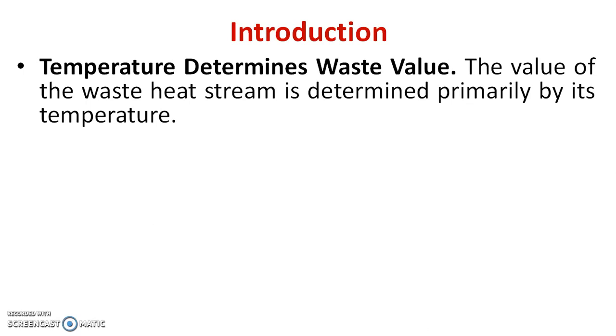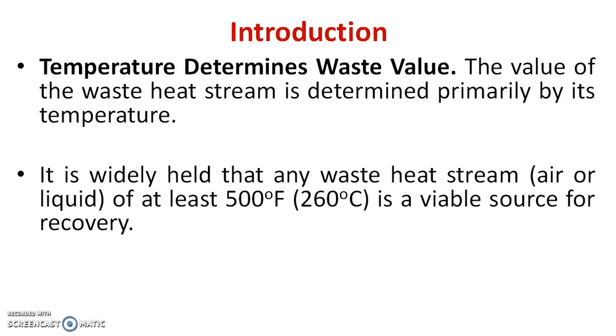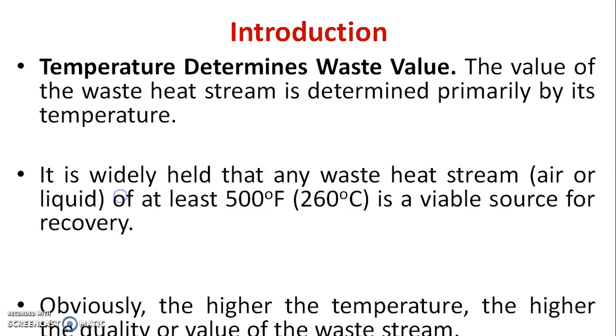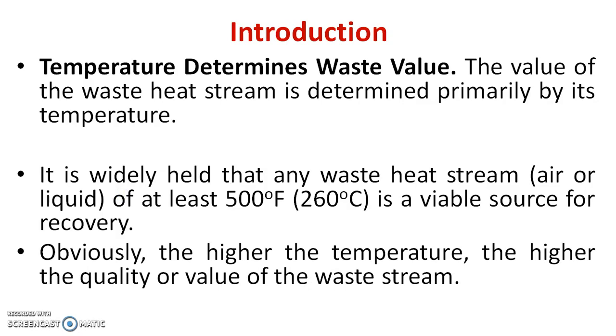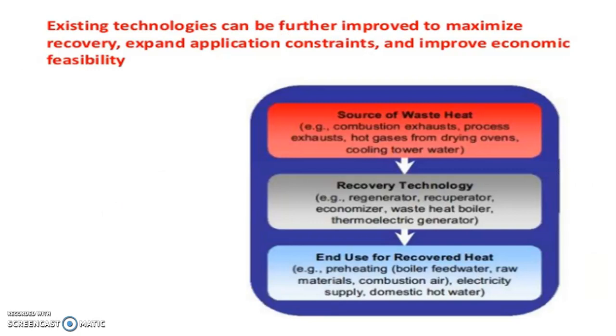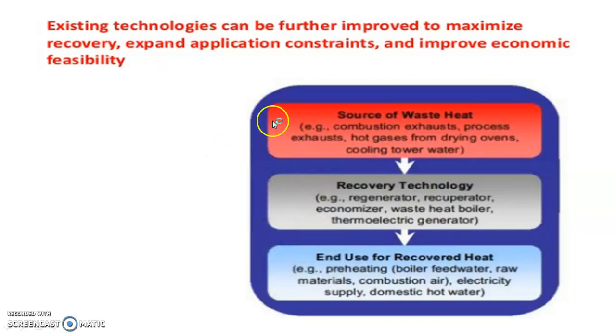Temperature determines waste heat value. The value of the waste heat stream is determined primarily by its temperature. It is widely held that any waste heat stream of at least 260 degrees centigrade or 500 degrees Fahrenheit is a viable source for recovery. Obviously, the higher the temperature, the higher the quality or value of the waste heat. So what are the sources of waste heat? Here you will see combustion exhaust, process exhaust, hot gases from drying steam, drying ovens, and cooling tower water. So these are the sources of waste heat.